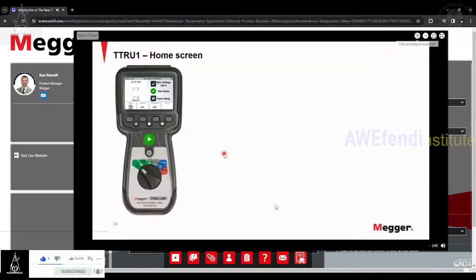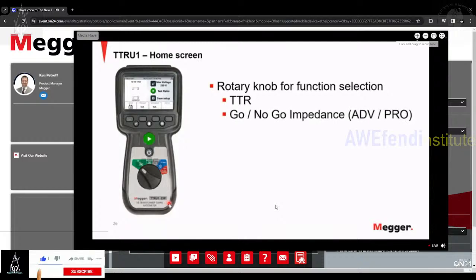Looking now at the user interface of the product, this is what you will see when you come to the home screen. You get the ability to change voltages, you get the ability to start the test. But if we look down below, that is where you will find your different test modes or different test capabilities of the product. Of course, we have the TTR test. In the advanced and the pro model, you will have the go, no go impedance, where we're looking for the shorts, the opens, the transformer core doing its job. And then finally, the short circuit impedance measurement, where we will give you that value compared to nameplate.